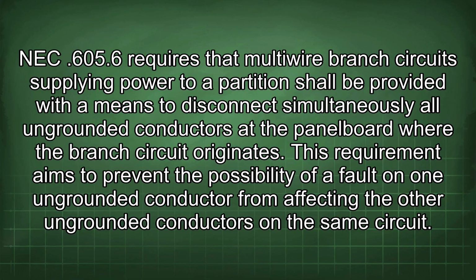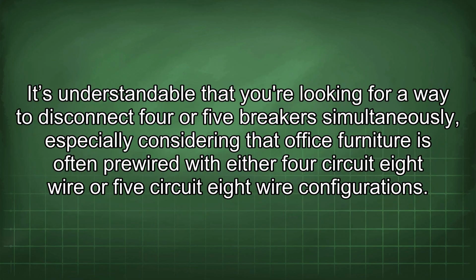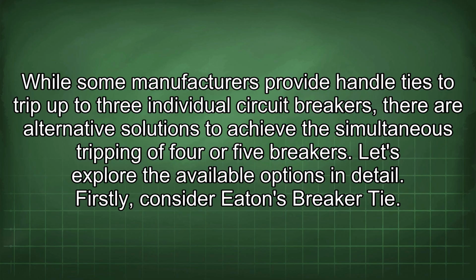It's understandable that you're looking for a way to disconnect 4 or 5 breakers simultaneously, especially considering that office furniture is often prewired with either 4-circuit 8-wire or 5-circuit 8-wire configurations. While some manufacturers provide handle ties to trip up to 3 individual circuit breakers, there are alternative solutions to achieve the simultaneous tripping of 4 or 5 breakers. Let's explore the available options in detail.